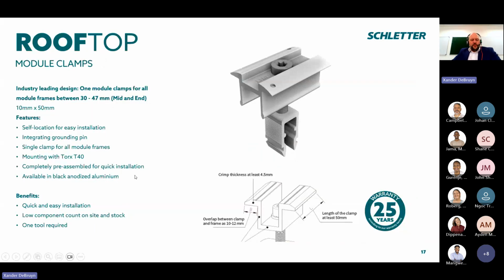All right. So the first thing that I like to consider in terms of Rooftop is we're protecting the module at the end of the day. So we're clamping down the module. We have what we call our ProLine module clamps that are designed to be compatible with all modern modules. It's designed to handle frame heights between 30 millimeter and 47 millimeters. I know that 15 years ago, there was a lot of 50 millimeter thick module frames. If they do come back at some stage, we will take it into account. But for the moment, this covers pretty much everything we're encountering on the South African market. All of the top module manufacturers have a similar requirement in terms of 50 by 10 clamping zone, which is covered in the design.